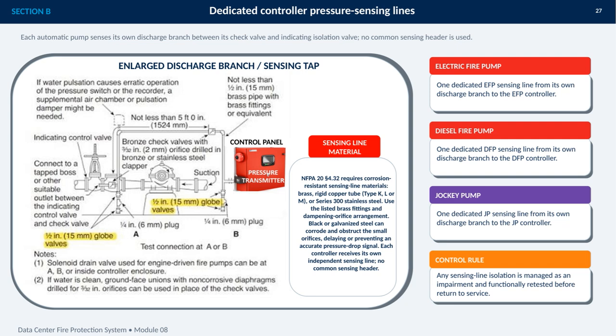NFPA 20, Section 4.32, requires corrosion-resistant sensing line materials such as brass, rigid type K, L, or M copper tube, or Series 300 stainless steel. Black or galvanized steel can corrode and obstruct the small orifices, delaying or preventing an accurate pressure drop signal.